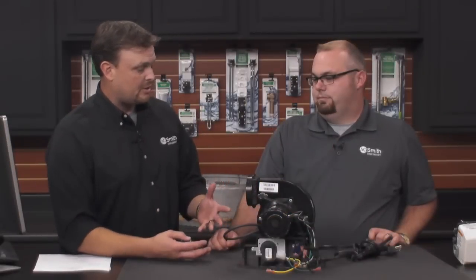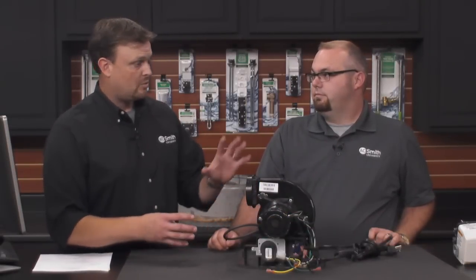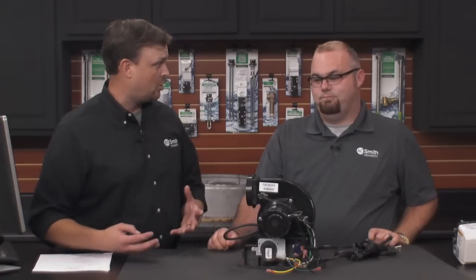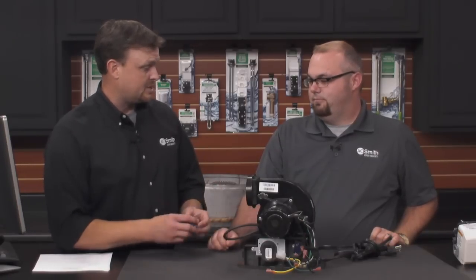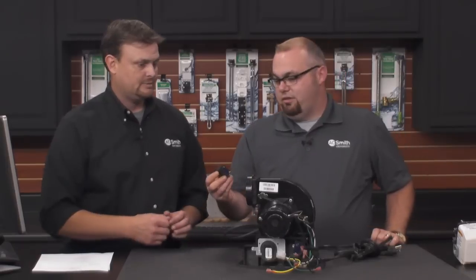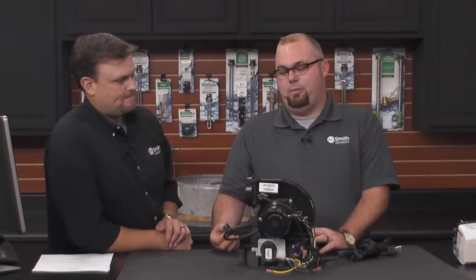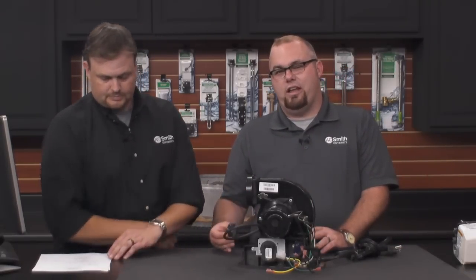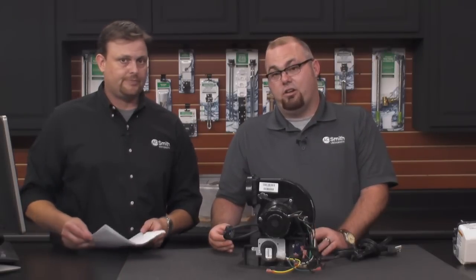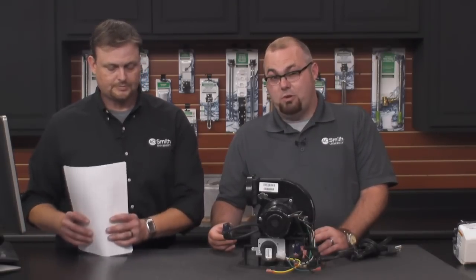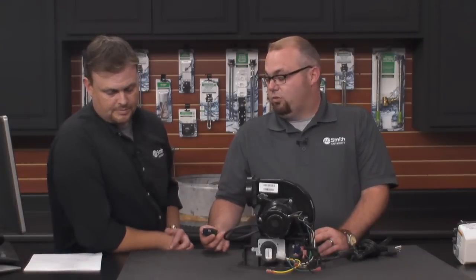Before, if the capacitor was bad on a blower with the older style, we would have to replace the whole blower. Now this comes with a separately replaceable capacitor. Yeah, the newer blower motor comes with a separately replaceable capacitor. So if you're ever having an issue, or say you were getting an error code where the blower was supposed to be running, but it's not, on the old school heaters, you had to replace the whole blower. If you tested and you had power and the blower wasn't started. But on this one, we have this capacitor, and it's something you can replace by itself.